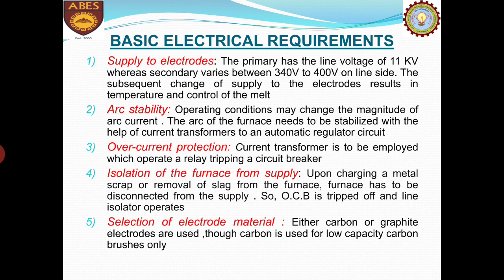Now tripping can be due to 11 kilovolt main voltage fluctuation as well, but we have to provide some sort of protection for the overcurrent conditions. Now, isolation of the furnace from the supply. When metal scrap has to be charged into the furnace and we have to remove slag from the furnace, the furnace has to be disconnected from the supply. So for this purpose we employ basically an isolator switch which is connected between the oil circuit breaker and the furnace transformer. As soon as we need to isolate for the charging purpose or for the removal of slag, the oil circuit breaker is tripped off and the line isolator will be opened.